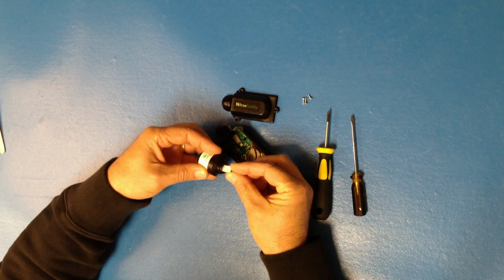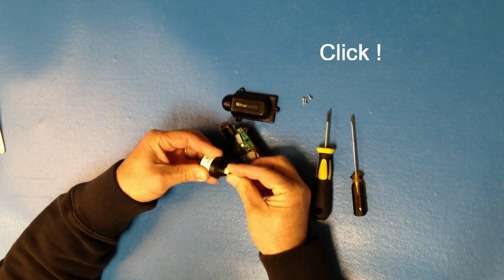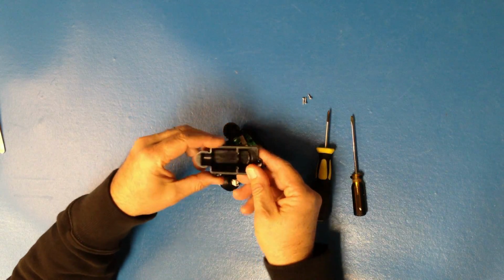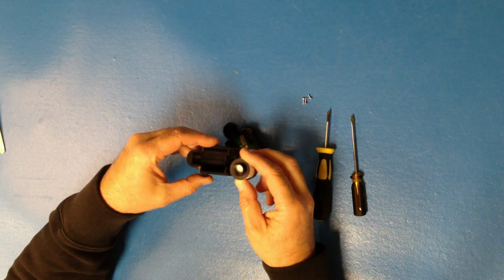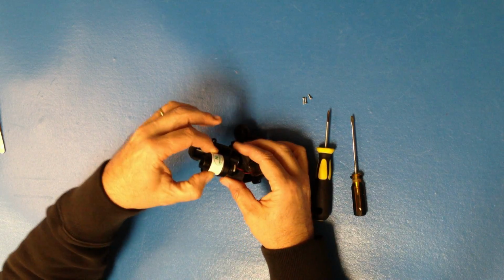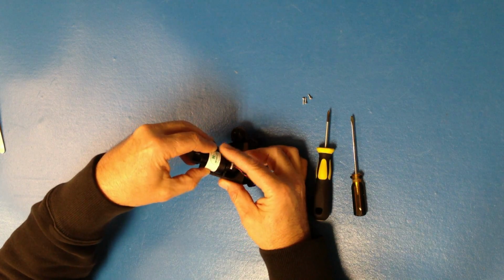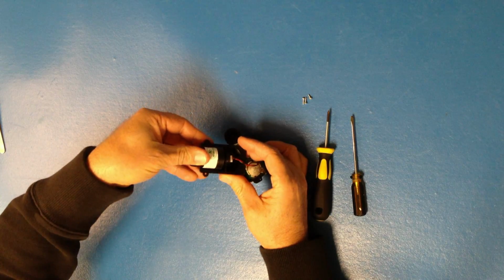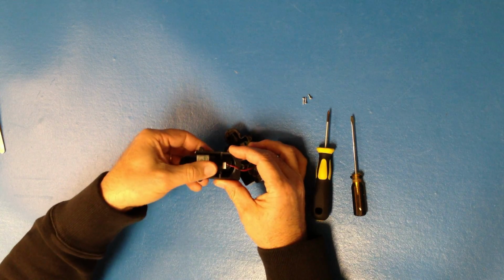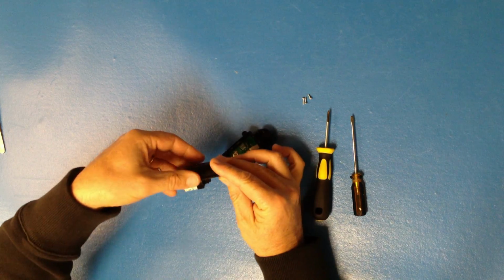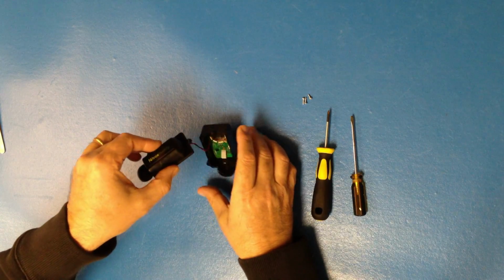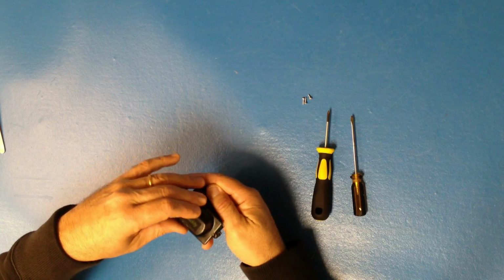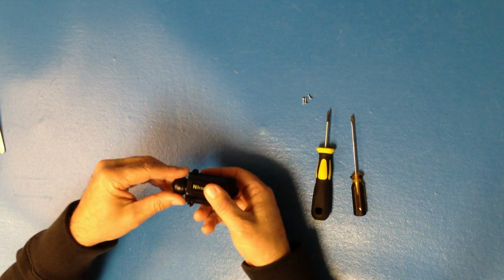Push the connector until you hear the latching mechanism securing the 2 connectors. Then place the oxygen sensor in the cavity of the top half of the housing. First, position the back of the sensor, then push in the front. The oxygen sensor should be firm in place. Now you can reassemble the 2 halves and secure them with 3 screws.